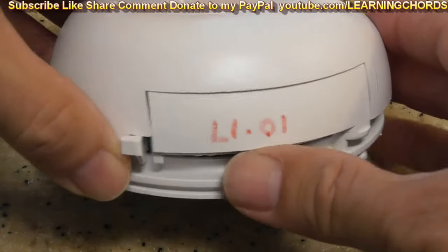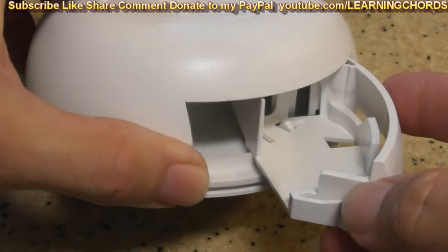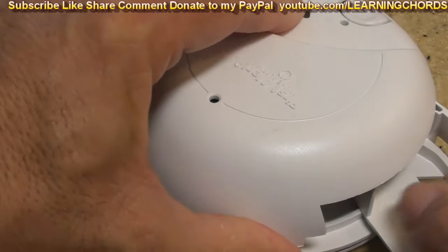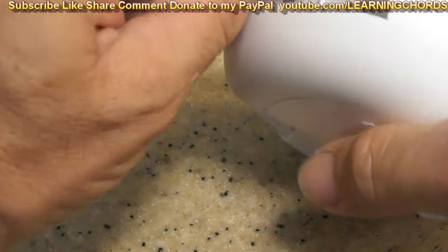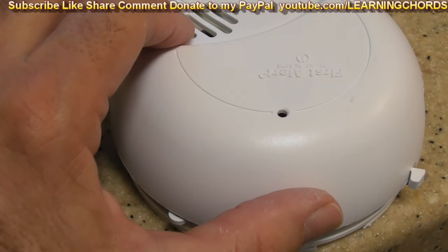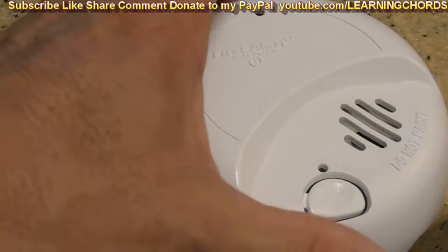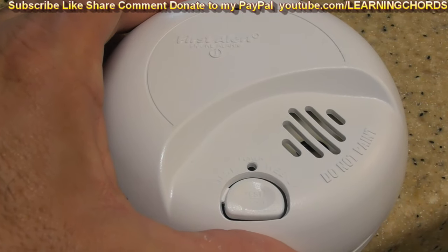You can see I installed it in 2017. That's the battery compartment over there with new batteries in it. But if you get that chirp sound, that's probably what's going on — it's old, it's defective, the battery is dead, or it's just got too much dust on the sensor. At that point, spend the money and replace it to protect your life.